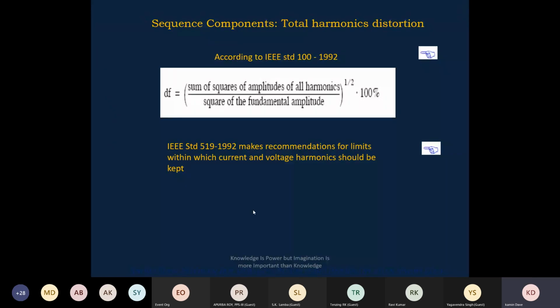So the distortion factor is also important, from equipment to equipment and in a power system network. Like how much it should be in a 220 kV network, how much in 400, and if HVDC is installed, how it should be in that. So the harmonic distortion factor has to be defined for the network. Otherwise, it will damage the equipment and lines and cables, and there will be frequent failures of the equipments. Similarly, IEEE standard 519-1992 also gives many recommendations of the harmonic limits of the equipments, if someone is interested, they can go to 519-1992.